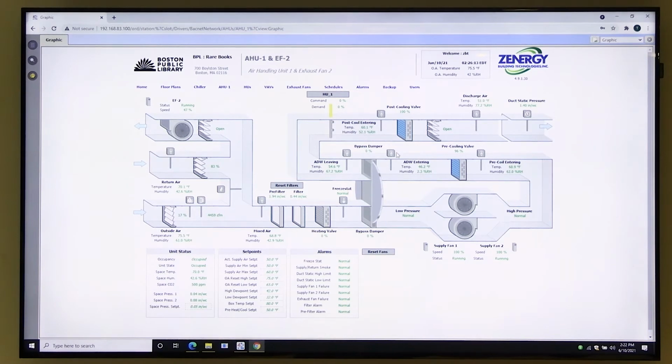This wheel here, we mentioned that. This is kind of a funny wheel. It's really just for reheating during dehumidification. So the idea here is in the cooling season, we're going to have this warm air coming in here, this warm mixed air temperature hitting the wheel. We're then going to cool it with what's called the pre-cooling coil here.